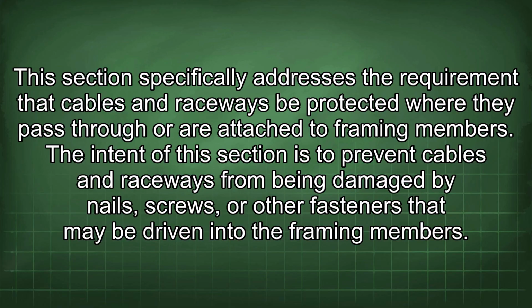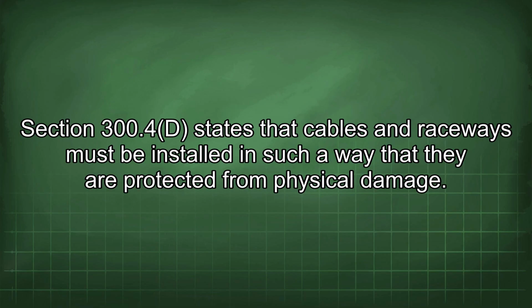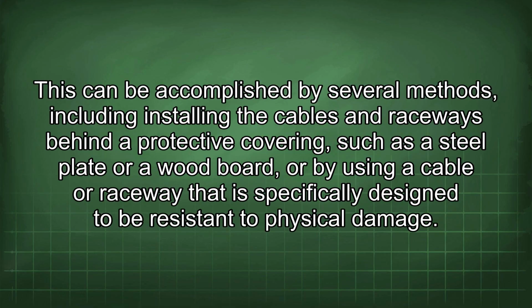The intent of this section is to prevent cables and raceways from being damaged by nails, screws, or other fasteners that may be driven into the framing members. Section 300.4d states that cables and raceways must be installed in such a way that they are protected from physical damage.